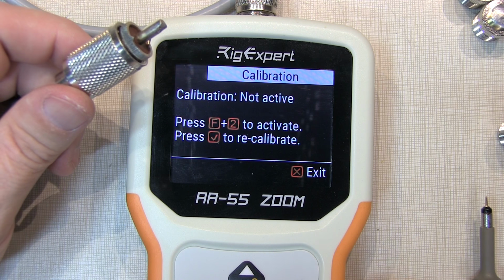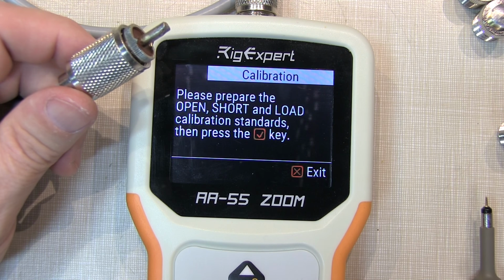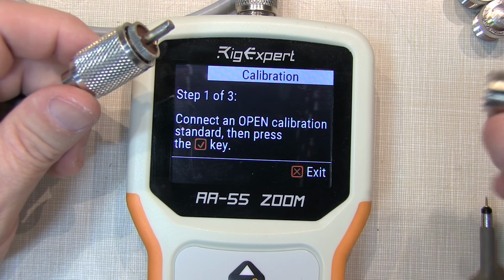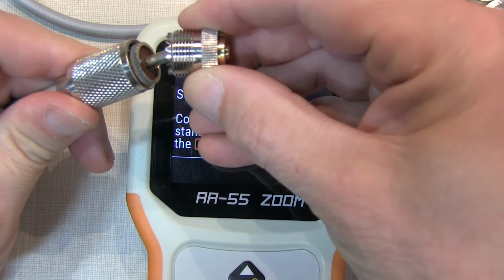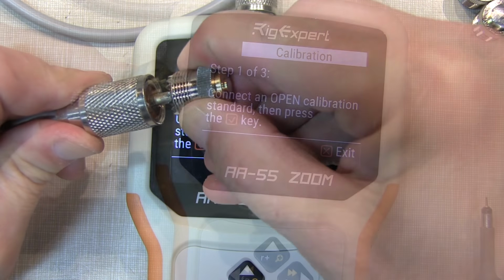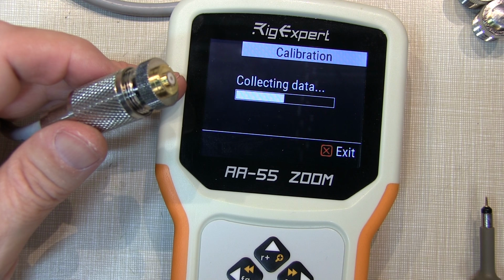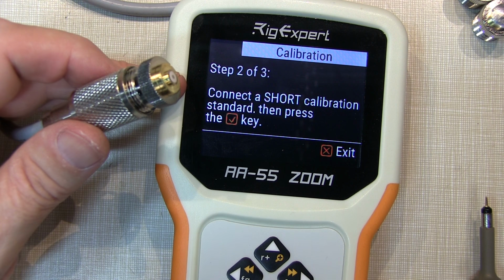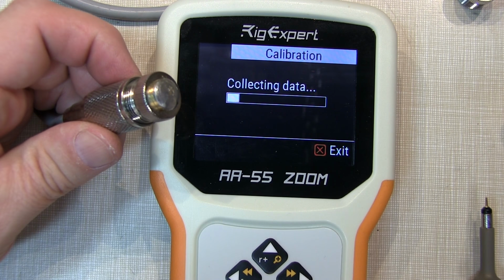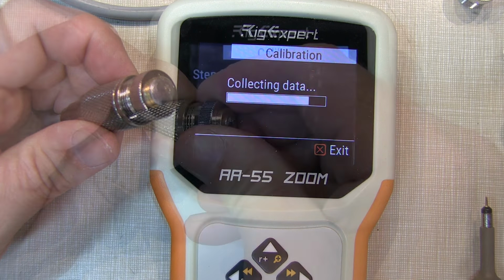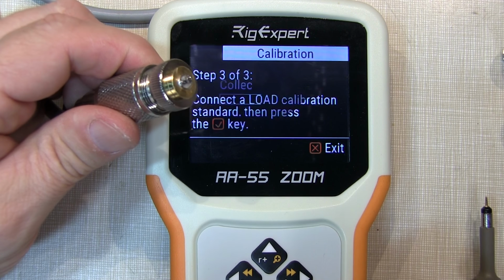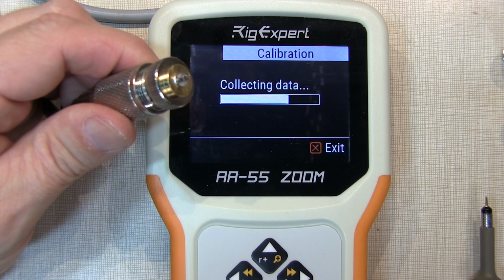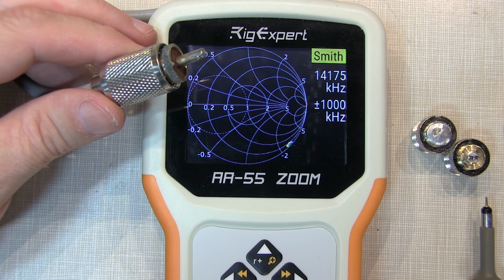Okay, so we'll start the calibration process, and it tells us to prepare our standards. Let's connect the open to the end of the cable first, and we hit OK, and it's collecting data on the open. Next we do the same for the short. Short's connected, hit OK, collect the data on the short, and connect the load, and collect the data with the load. So let's see how effective our cal standards were.